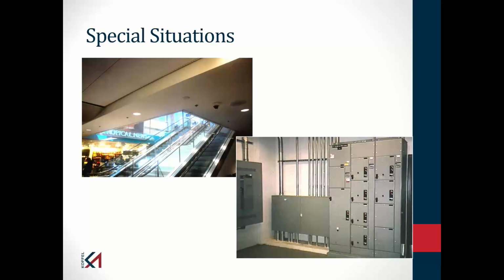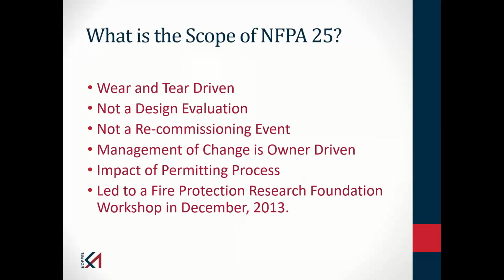So that basically gets us through the types of things I wanted to cover in NFPA 13. I said I wanted to spend a little bit more time on NFPA 25 because as facility personnel, you are probably going to deal with NFPA 25 more than you deal with NFPA 13. NFPA 25 is where I go to define the inspection, test, and maintenance requirements for all water-based fire protection systems. So the sprinkler system, the standpipe system, the fire pumps you may have, tanks if you have them, the inspection, test, and maintenance requirements are found in NFPA 25.